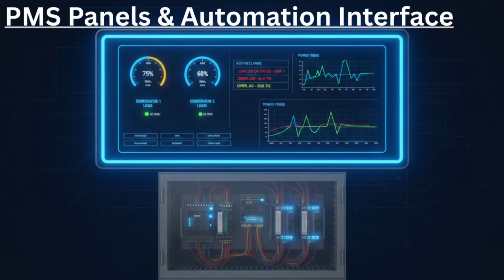PMS panels or automation interface. PMS is controlled via digital control panels, PLC systems, and human-machine interface, HMI, screens. Engineers can monitor generator status, load percentage, alarm history, synchronization, and reactive power from the interface. The interface provides real-time data visualization, allowing operators to make informed decisions or perform manual override if necessary.